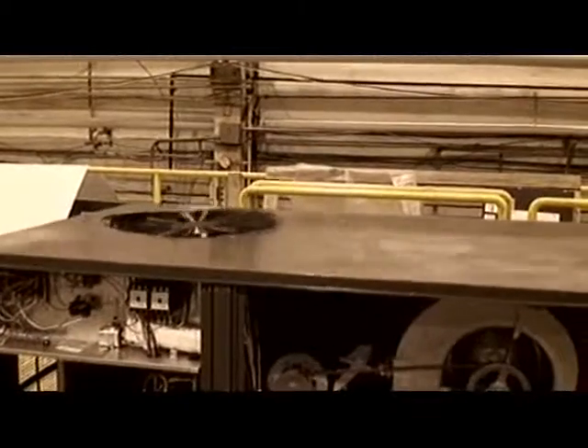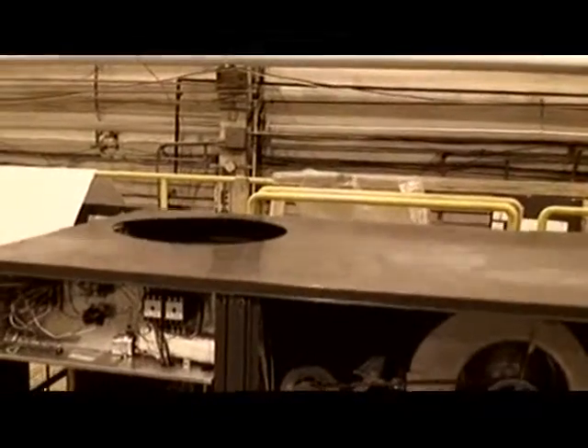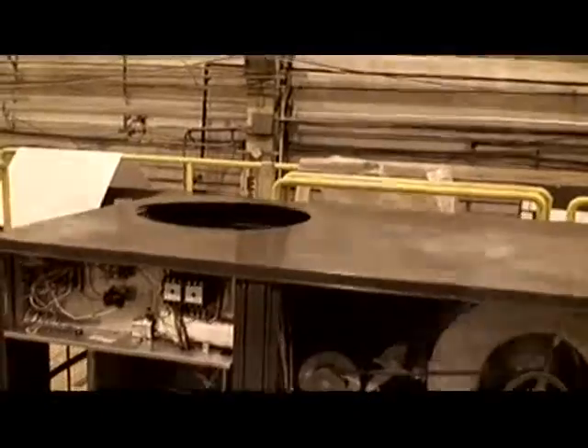Not only did the condenser fan section drop into the unit, it did substantial damage to the condenser coil within, basically classifying the unit as unusable by Carrier standards and no doubt many others. In addition, we found the ground wire came completely off. This is a safety issue.